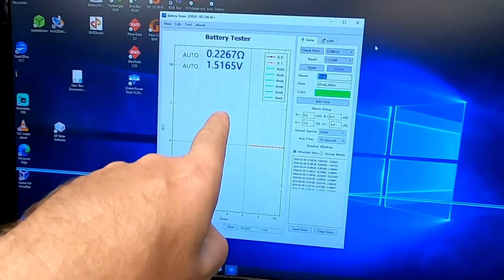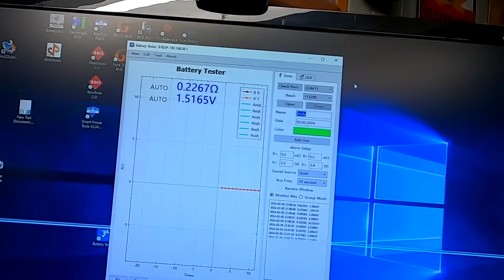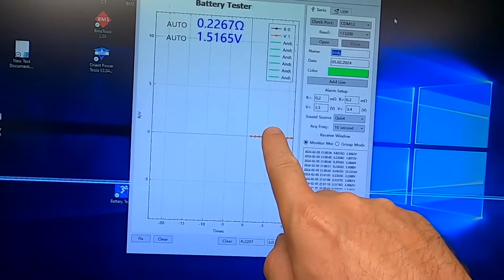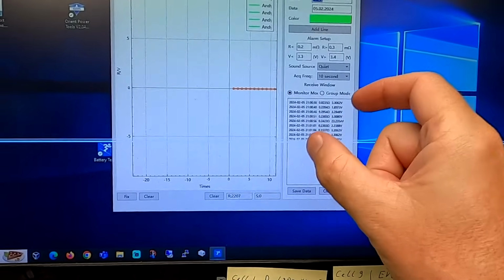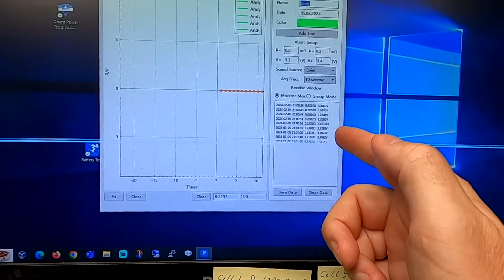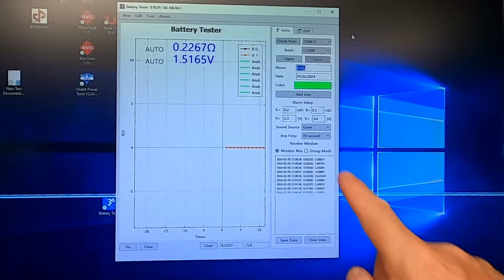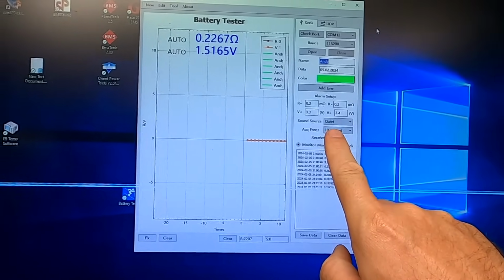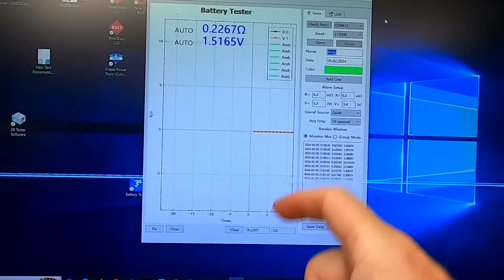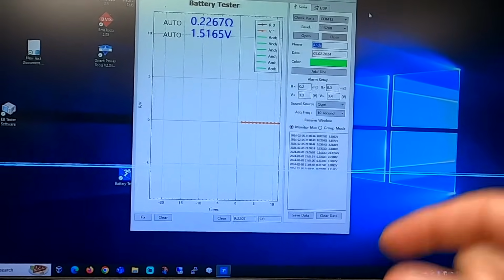So the computer software is absolutely garbage. I really thought they'd be building a nice graph and that we could trigger the actual measurement moment somehow. But this one works on a timer, so you have to change your probes every 10 seconds, which in reality is only 6 seconds, to the next battery and make sure the reading is correct.